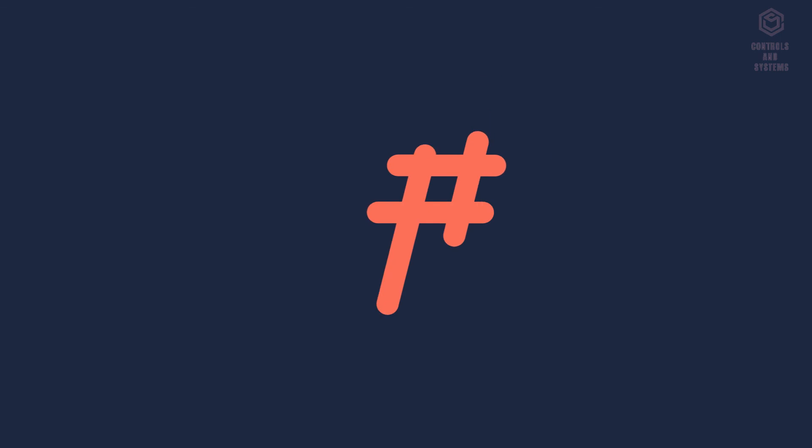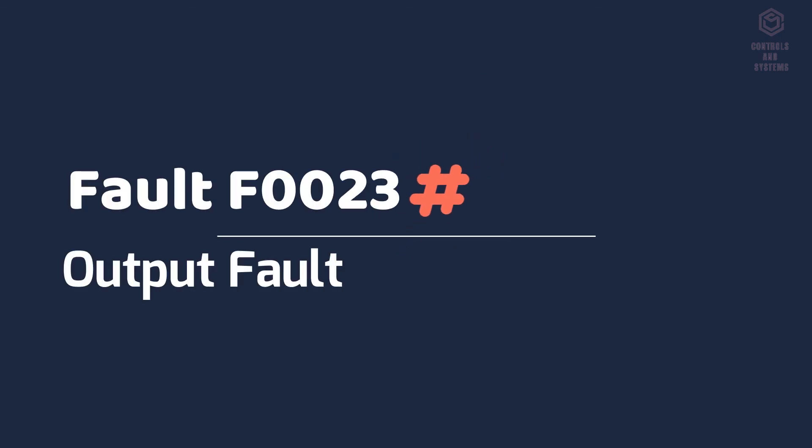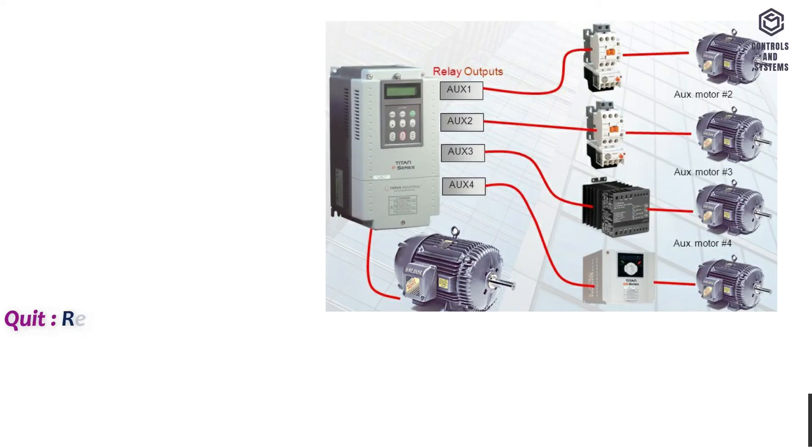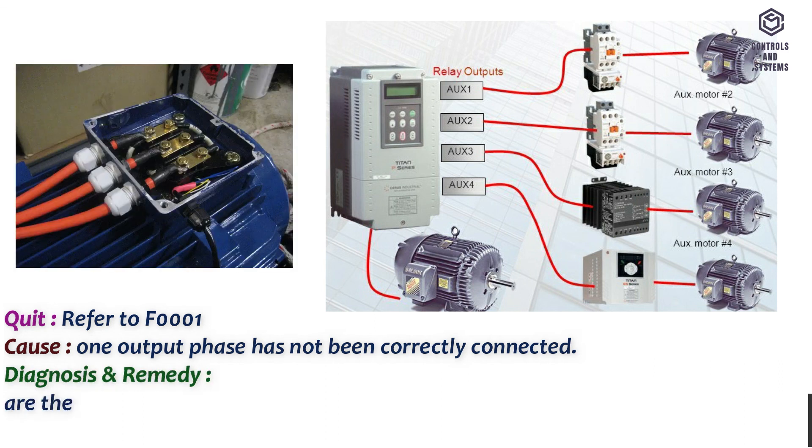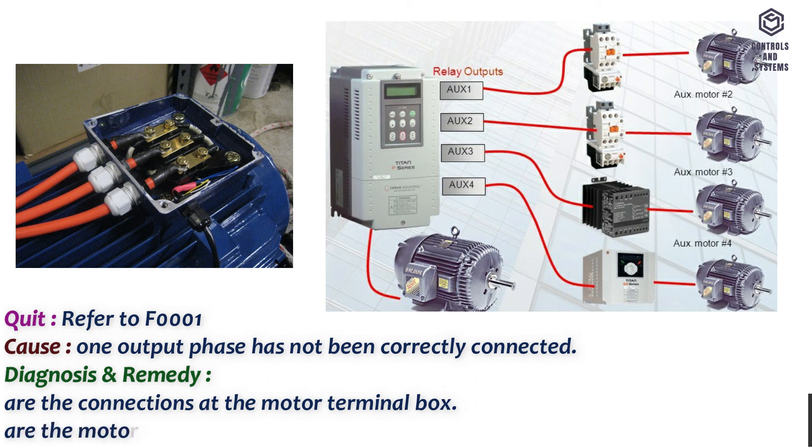Fault F0023 output fault. Quit: refer to F0001. Cause: one output phase has not been correctly connected. Diagnosis and remedy: Are the connections at the motor terminal box? Are the motor cable connections at the inverter?